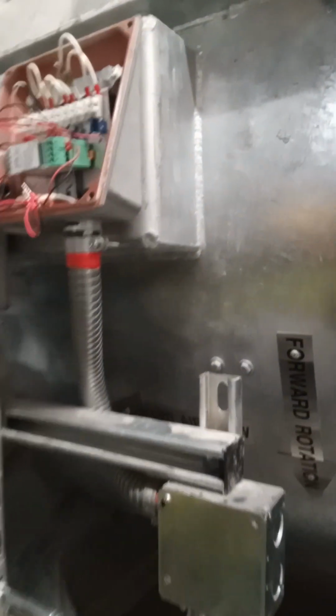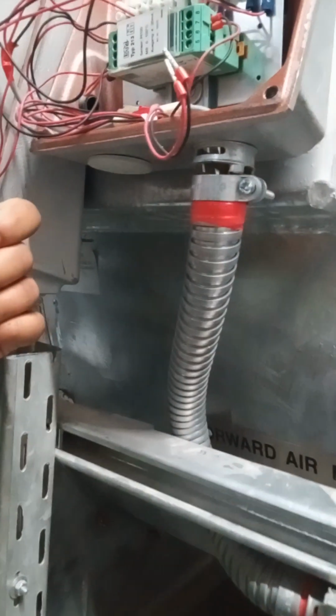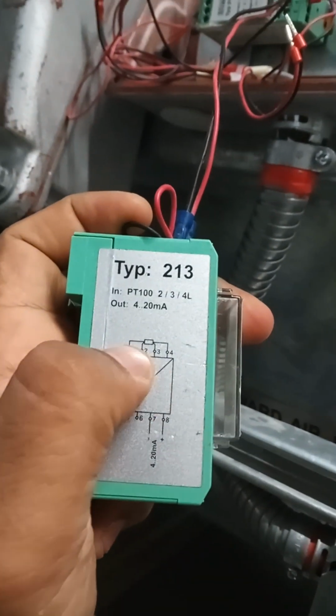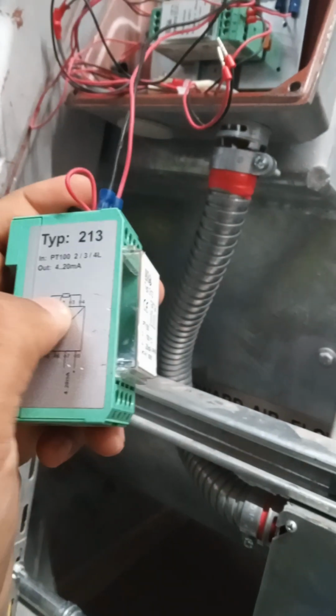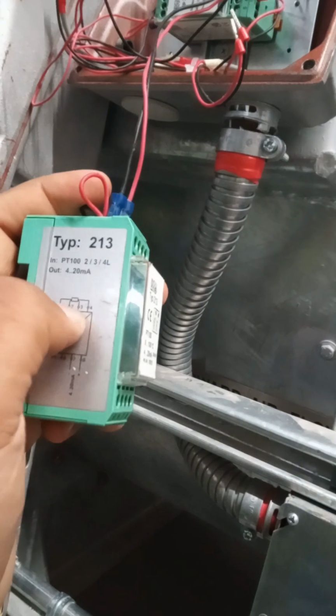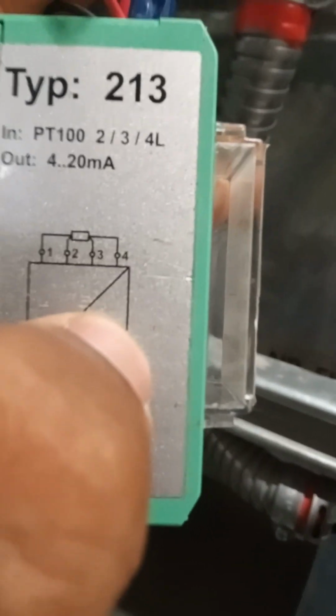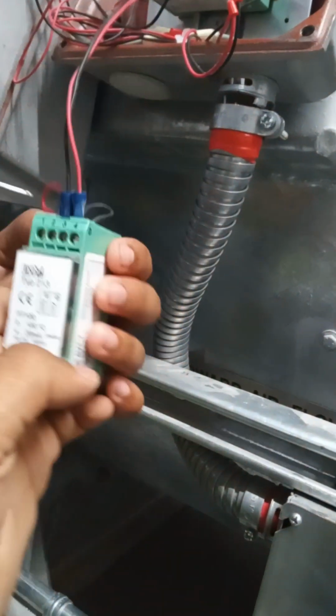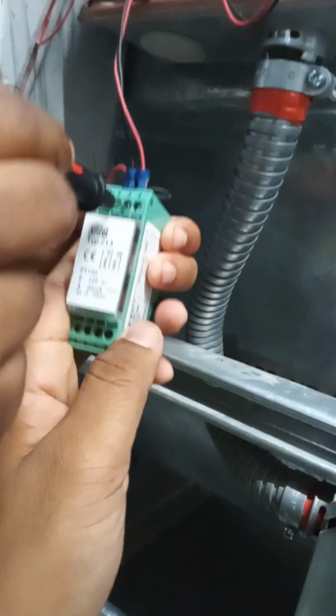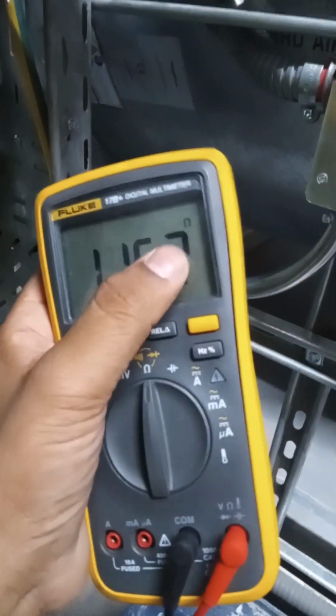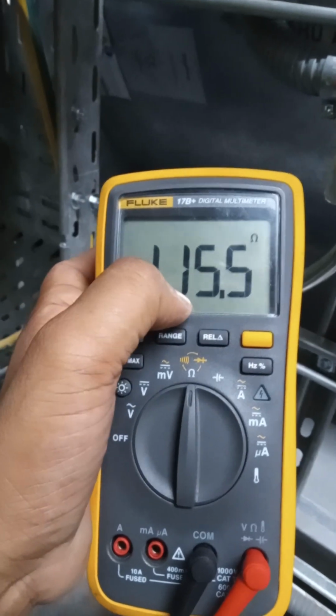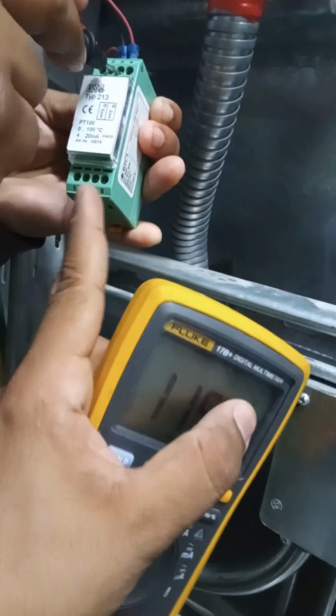Okay, I will tell how to check whether the sensor is working correctly or not. This is the sensor. You are getting a PT100 resistance from the field, and it is connected to 2 and 3. So this 2 and 3 is a resistance. We can check this resistance value at 2 and 3, and the value shall be around 110 and above. Can I just connect the multimeter here? At 2 and 3, set the meter to ohms, not mega ohms. 111 shall be there. You don't measure here. This is the milliamps output, measured as per the drawing. Here you have to measure. If you get 105 from the field side, it is okay.